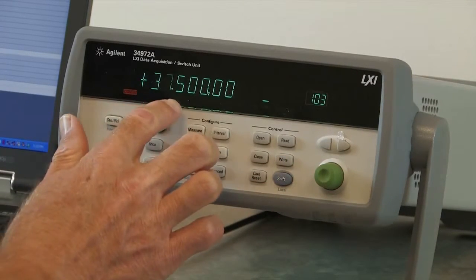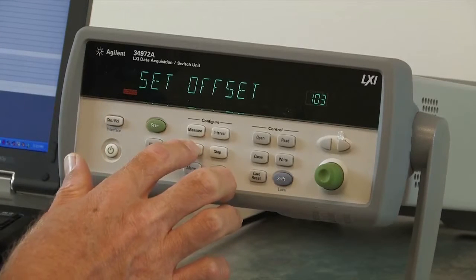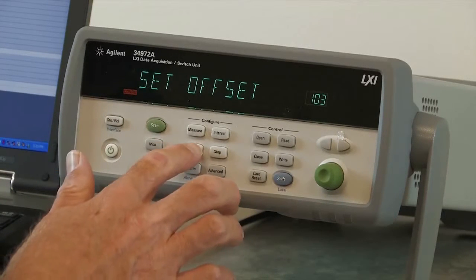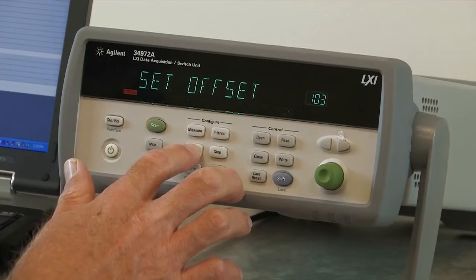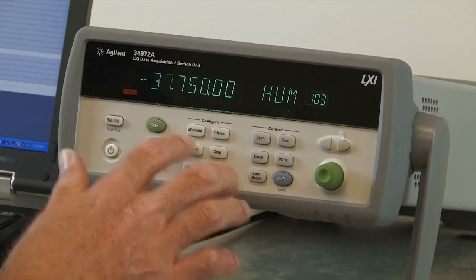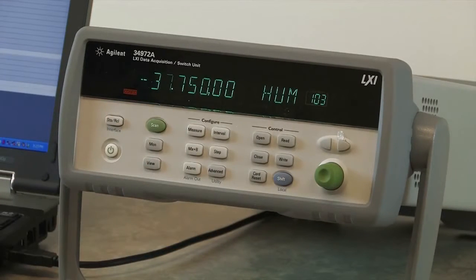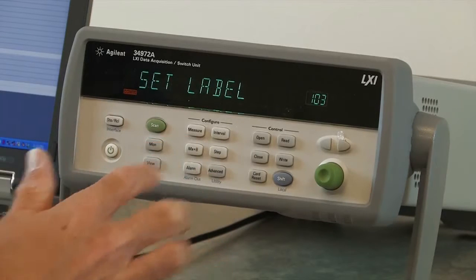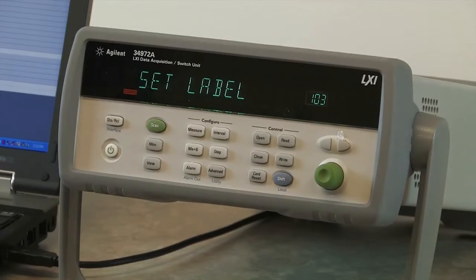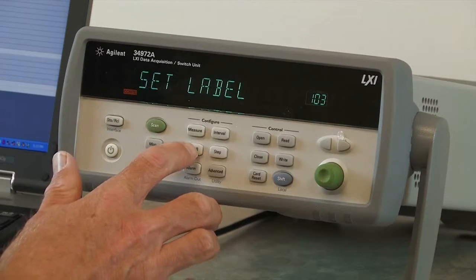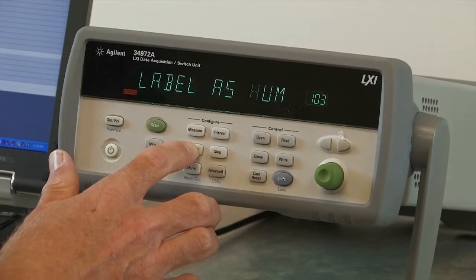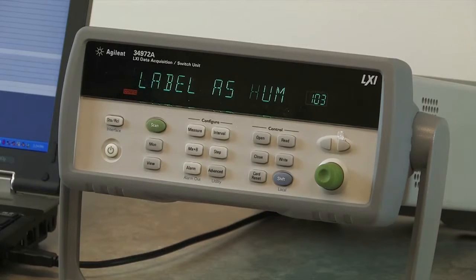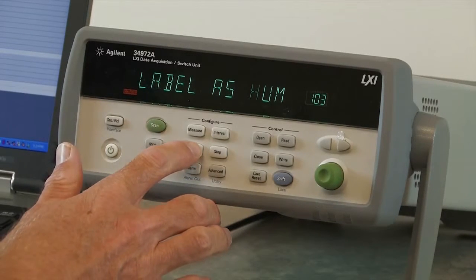I'm going to set the gain to 37.5. I'm also going to set an offset, and again from the datasheet, the offset I need to set is negative 37.75. Lastly, I want to set the units. Instead of being DC volts, I want to set a unit value that makes more sense for the measurement we're making. Since it's humidity, I've selected 'hum' as our label for this channel.